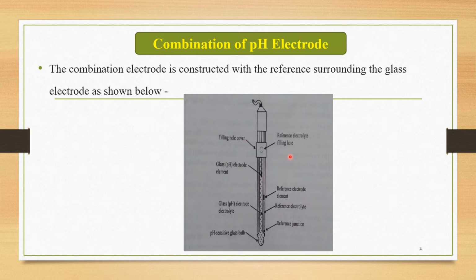At the upper part of this combination electrode, there is a reference electrolyte filling hole. From this hole we can fill the reference electrolyte, and this is the filling hole cover. This is a cover for this particular hole. So this whole part is called the combination type of electrode for pH measurement. It consists of both the reference as well as the glass electrode, and it is commonly called the combination electrode.